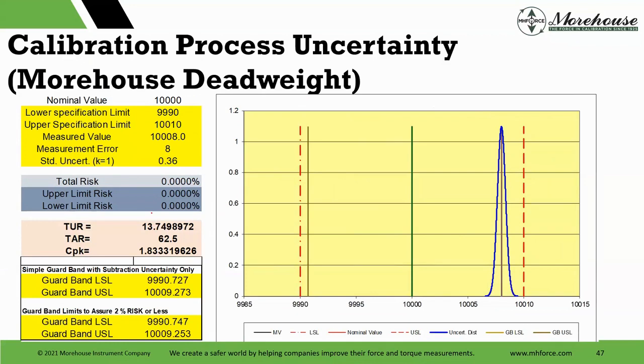TUR, we look at this, TUR 13, calibrating the TAR, which we haven't discussed. That's test accuracy ratio. I don't like that at all. But that's 62.5. And CPK is a concept I'm going to talk about because that really gives you some insight on the measurement location. And that's built into these sheets as well. So here we have our specification. We do the calibration. The measured value is 10,008.